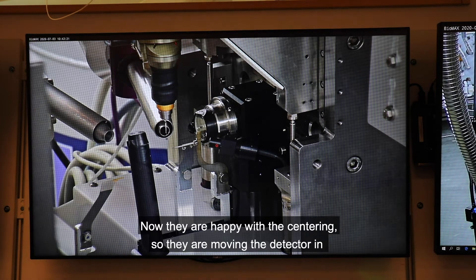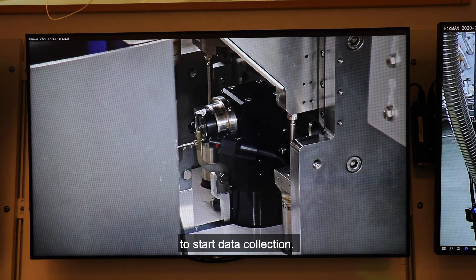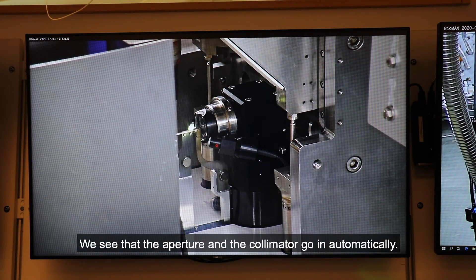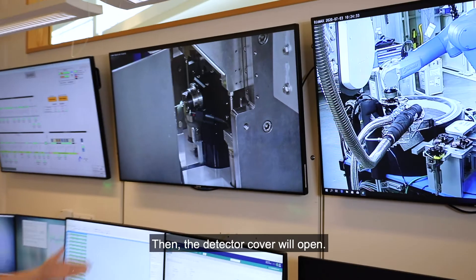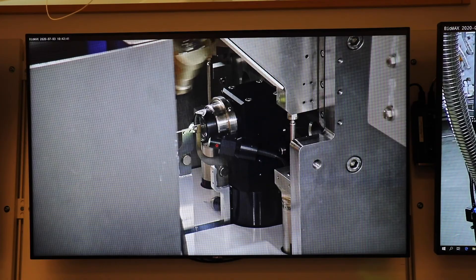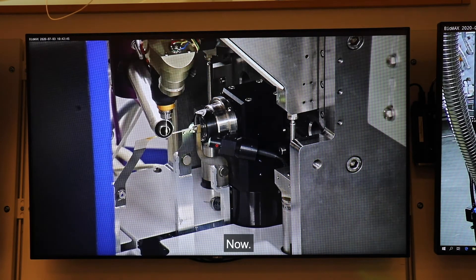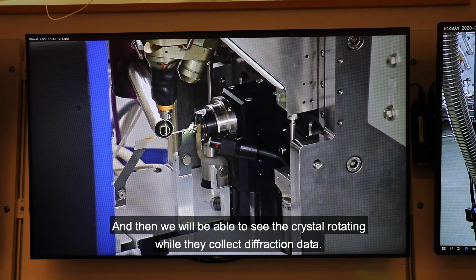Okay, so now they are happy with the centering. So they are moving the detector in to start data collection. We see that the aperture and the collimator go in automatically. Then the detector cover will open. Now.